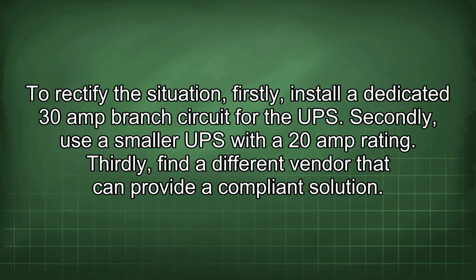To rectify this situation, firstly, install a dedicated 30 amp branch circuit for the UPS. Secondly, use a smaller UPS with a 20 amp rating. Thirdly, find a different vendor that can provide a compliant solution.